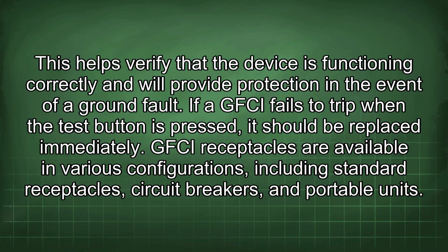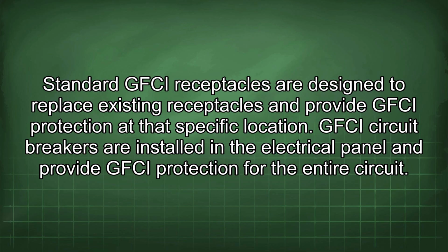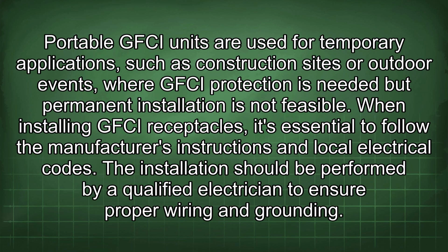GFCI receptacles are available in various configurations, including standard receptacles, circuit breakers, and portable units. Standard GFCI receptacles are designed to replace existing receptacles and provide GFCI protection at the specific location. GFCI circuit breakers are installed in the electrical panel and provide GFCI protection for the entire circuit. Portable GFCI units are used for temporary applications, such as construction sites or outdoor events, where GFCI protection is needed but permanent installation is not feasible.